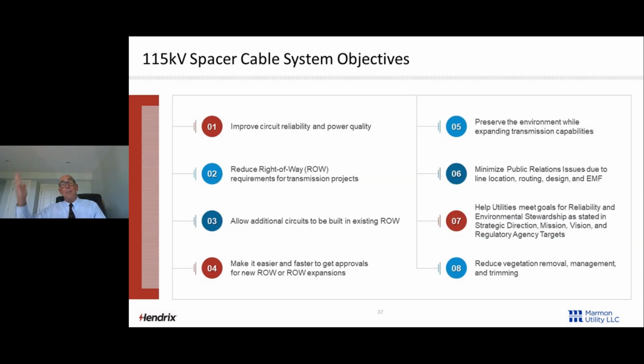The objectives, as you can imagine, are the exact same objectives that we had with 69 kV. We want to improve reliability and power quality. We want to reduce the right-of-way. We want to allow additional circuits to be built in that existing right-of-way. We want to make it easier and faster to get approvals for new right-of-way or right-of-way expansions. Telling the Public Utility Commission you're going to have a smaller right-of-way, have environmental stewardship, protect the flora and the fauna, and have a smaller carbon footprint is going to get you a quicker right-of-way permit.